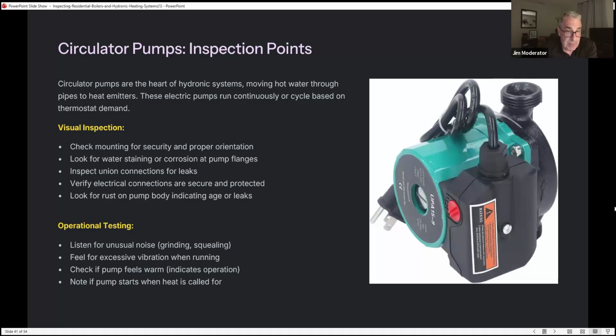You'll want to listen for any unusual noises like grinding or squealing, feel for excessive vibration when running, and check to see if the pump feels warm. Note if the pump starts when heat is called for. That's a little bit of a review here.